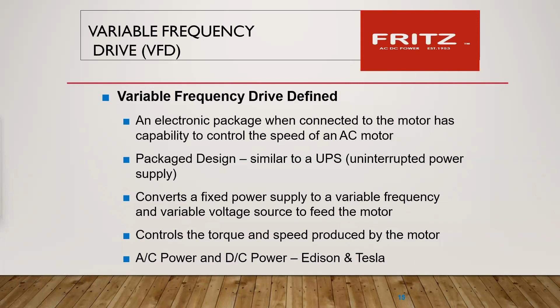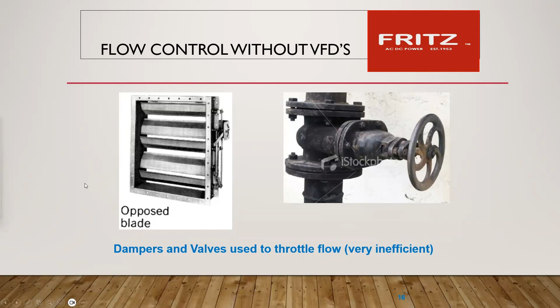But there's an amazing amount of dampers and throttles and valves that are still utilized in a circuit that you kind of just overlook or don't see. They were put in as design, and you need to look at those pressure drops and losses across them, because if you can do that with motor speed, you're immediately saving energy. So this is an example of a 50 horsepower motor with and without a VFD.